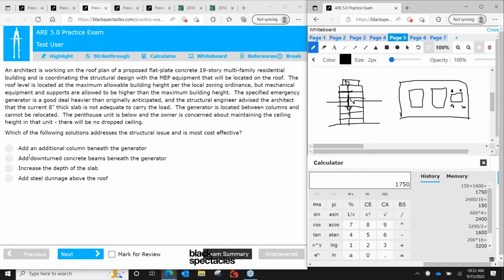Next, add downturned concrete beams beneath the generator. A downturned beam is an edge beam located under the slab perimeter, usually used in slab-on-grade situations. This would not be applicable in our case since the area in question is the roof and not the ground plane. Furthermore, adding a thickened beam element may also cause a change in ceiling height, and we noticed the owner is concerned about maintaining the ceiling height in that unit. So this would not be a good option for us.